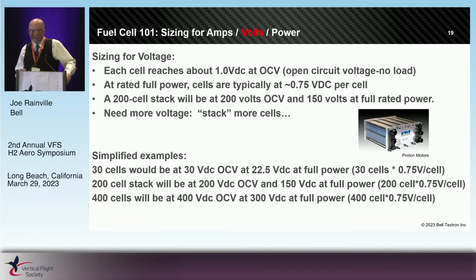Sizing for voltage. Each cell, as I said, is about 1 volt at open circuit voltage at no load, which means you're flowing reactants, but you're not yet pulling current. At full rated power, they're typically around 3/4 of a volt per cell. So a 200 cell stack is going to be about 200 volts at OCV and about 150 volts at full rated power. Need more voltage? Stack more cells.